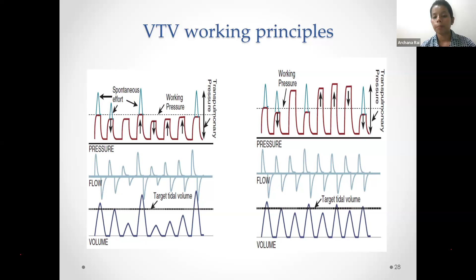And it has software so that the working pressure of the next cycle will be set as per the last breath of the same type, whether it was triggered or not triggered. If it was a triggered breath, it will see the last working pressure and the volume generated in that, and then for the next triggered breath, it will adjust according to the last triggered breath. And if it was only mechanical ventilator-induced inflations, then for the next ventilator-induced inflations it will use the previous ones in the same way.